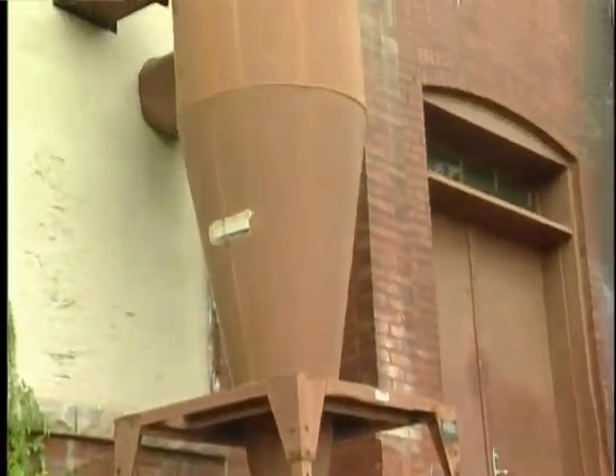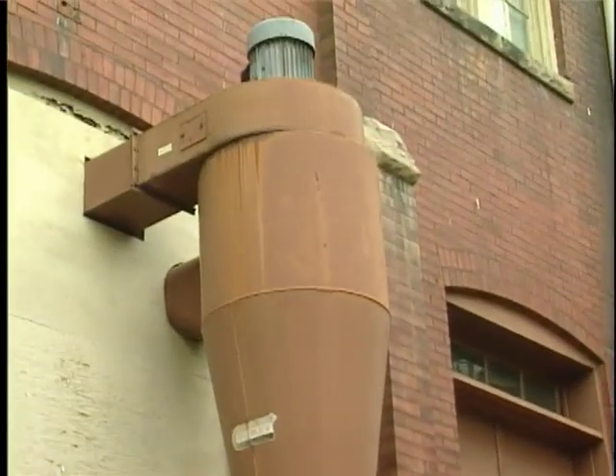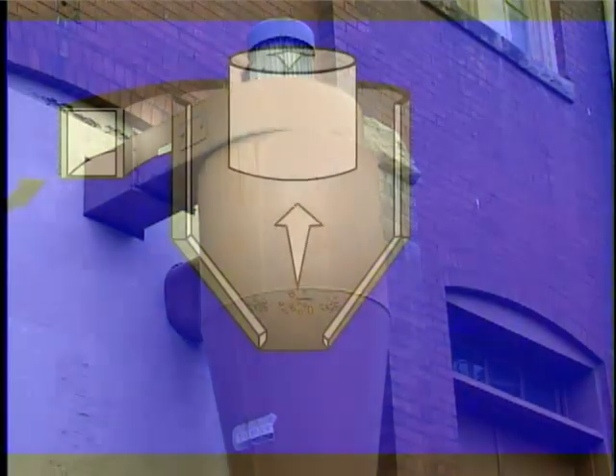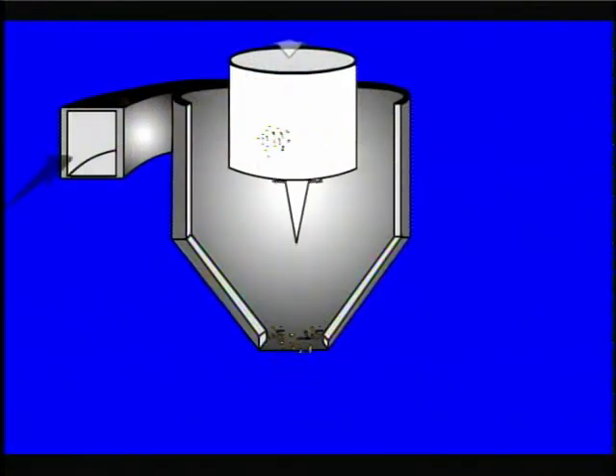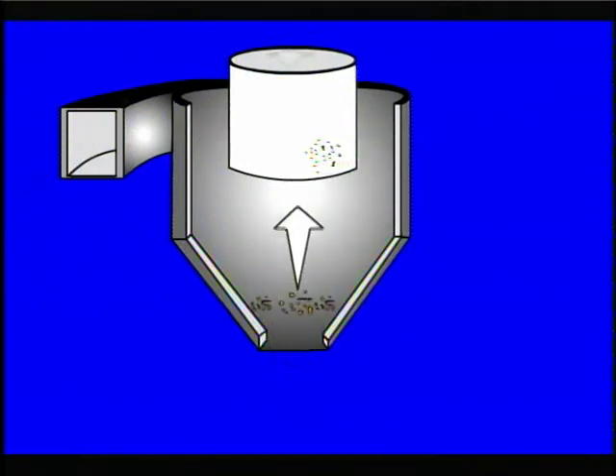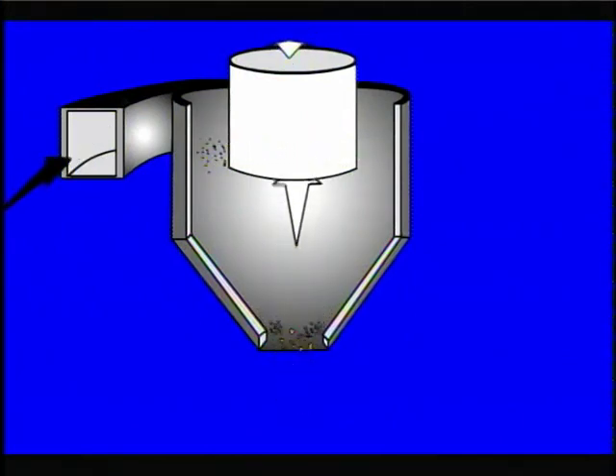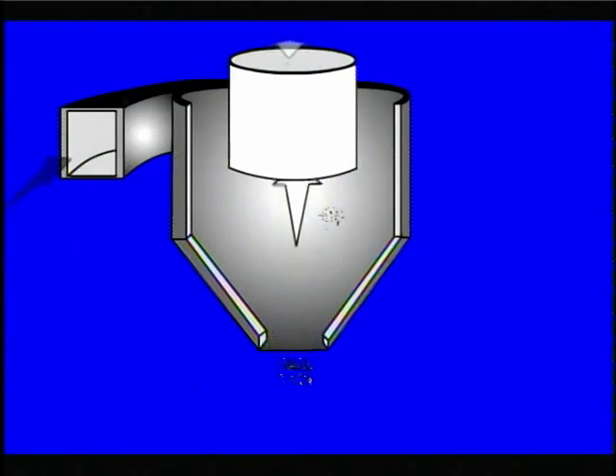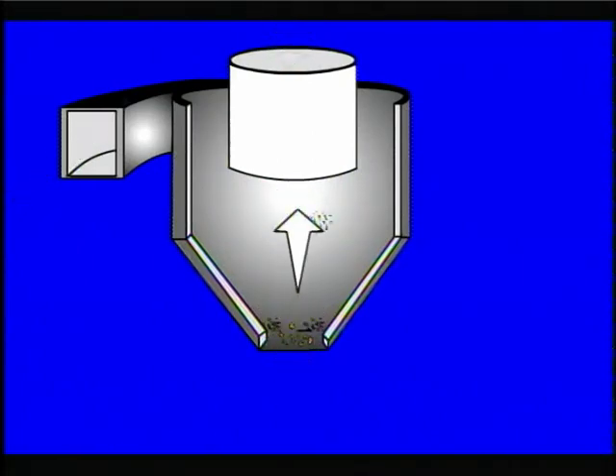The exit tube extends into the barrel section to a level below the tangential entry, in order to prevent direct discharge of the entering gases. Separation of the particles from the gas stream takes place during the outer rotation. Inertial forces imparted to the particles cause them to move to the wall of the cyclone. Since the gas stream velocity is very low near the wall, gravity causes the particles to move down the wall and out the bottom of the cone section.